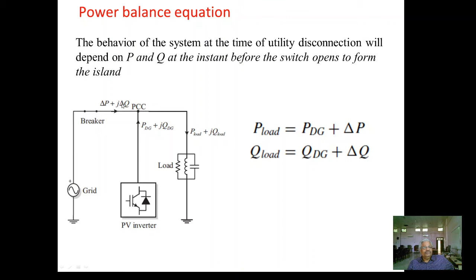Now, the important things are here. The present state of the islanded system, meaning after opening of the circuit breaker, depends on the values of delta P and delta Q just before the utility grid has been disconnected from the island. These values are denoted by delta P dash and delta Q dash. So these are the values of power from or through the grid before opening of the circuit breaker. After opening of the circuit breaker, this value will be 0.